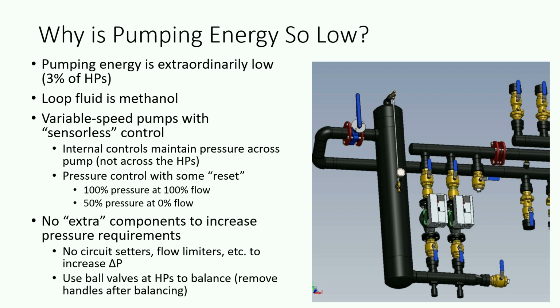Engineers put these components in for fear that flows might not be perfectly balanced. In reality, heat pumps are pretty tolerant to different flows, and I think there's too much emphasis put on trying to balance flows when that's not necessarily an issue. For this one, Buffalo Geothermal used ball valves at the heat pumps to balance. There were some heat pumps they had to lower the flow on, but they did it all by hand, and then they removed the handle on the balancing valve.